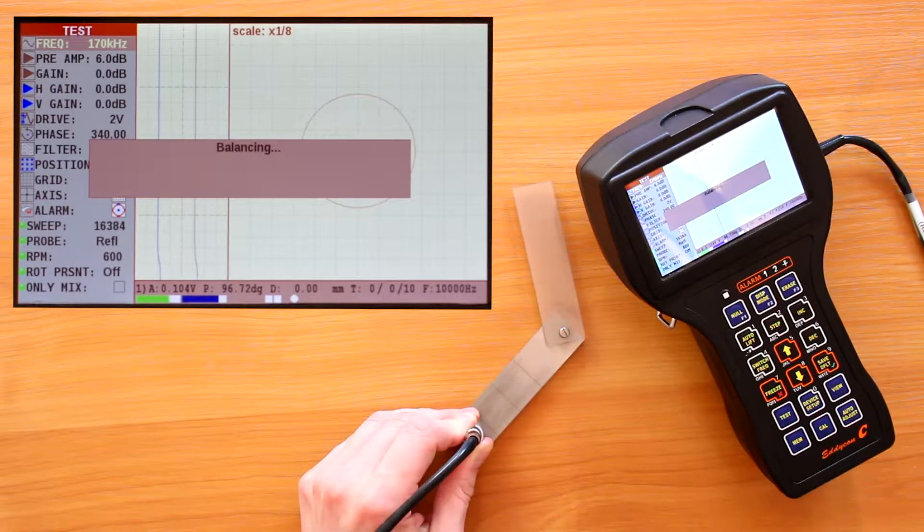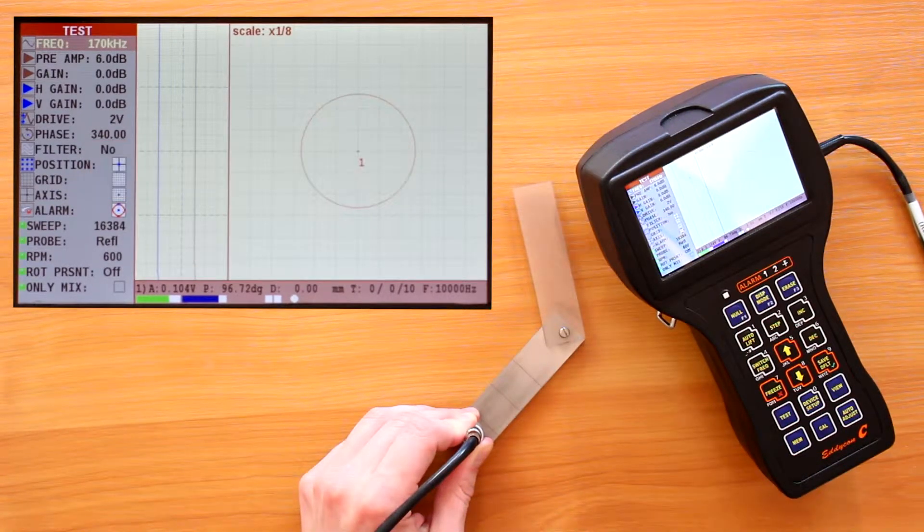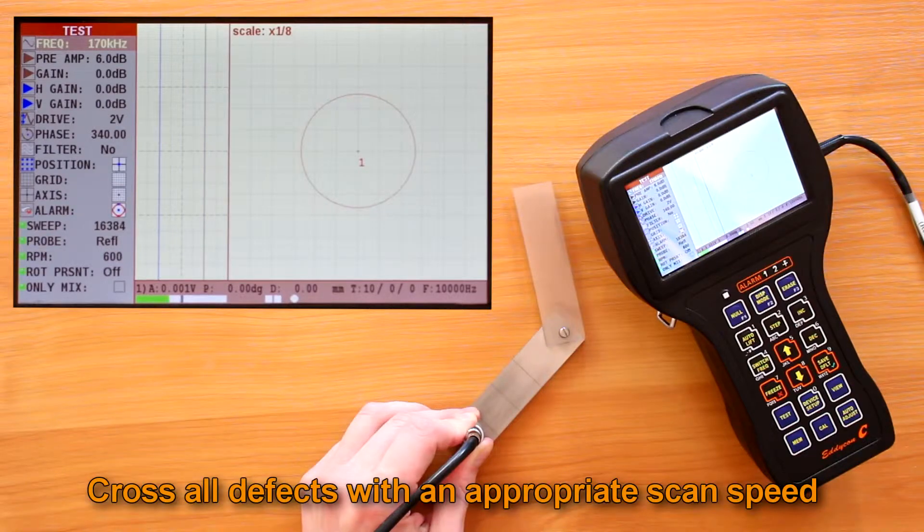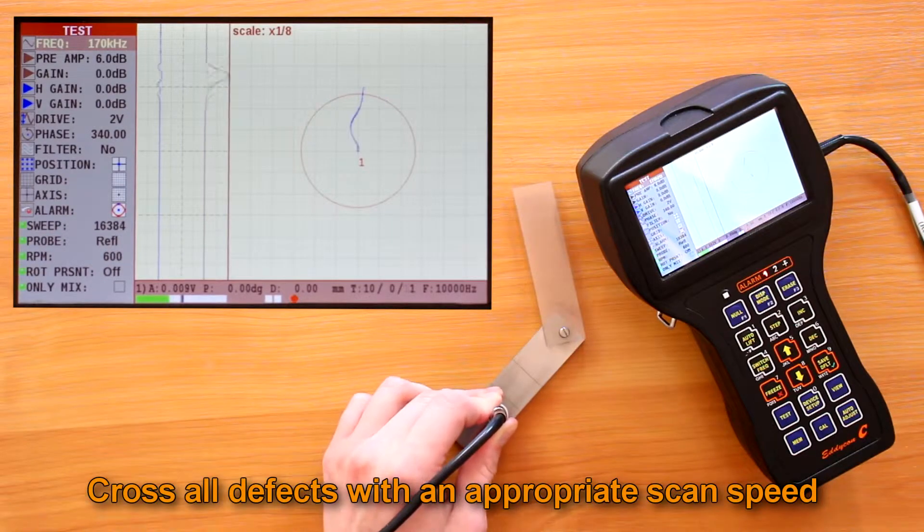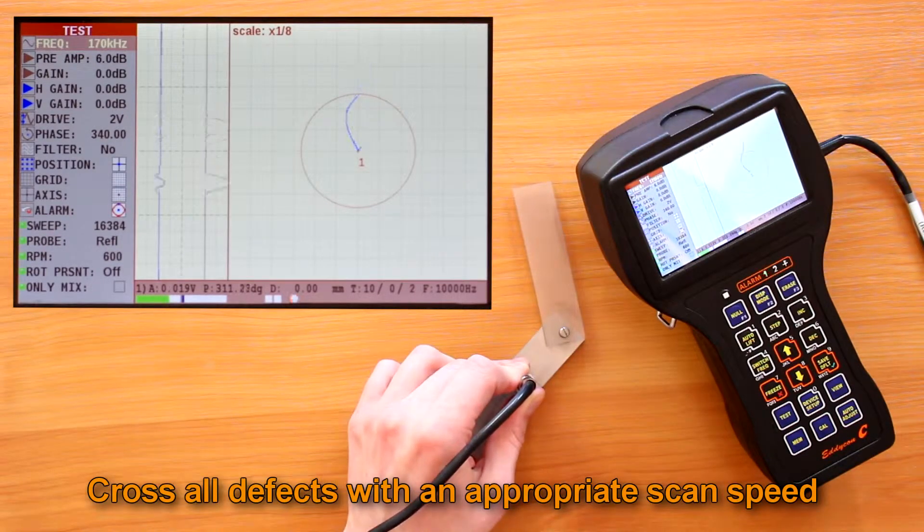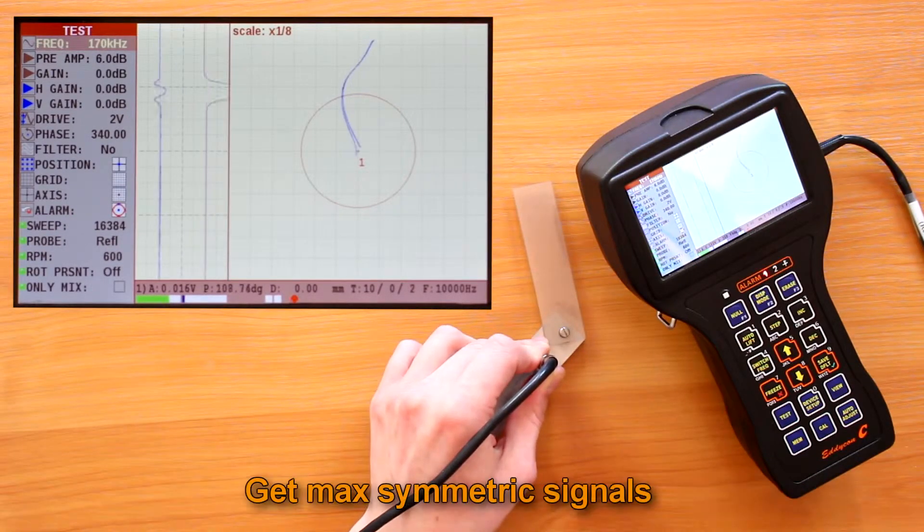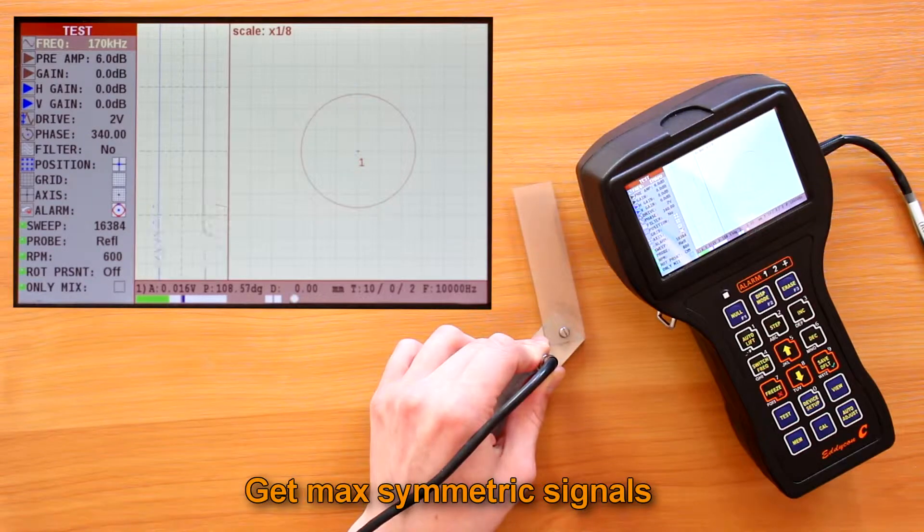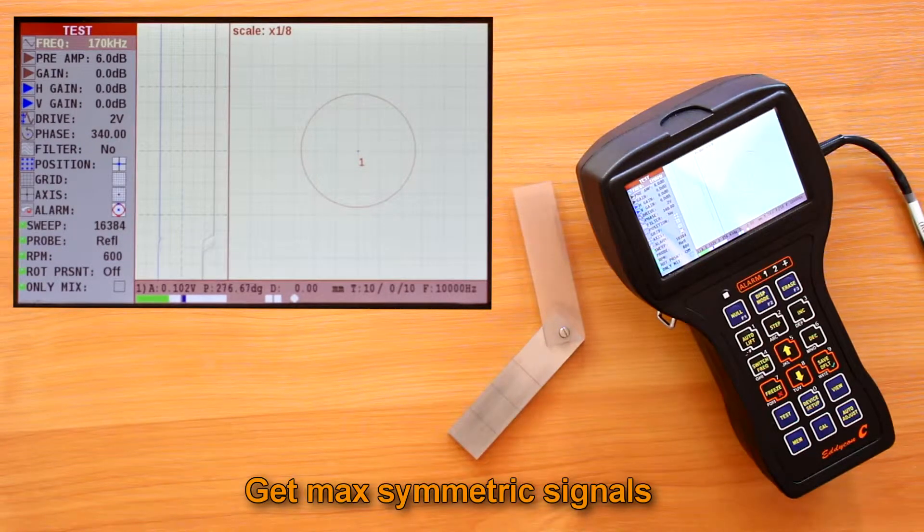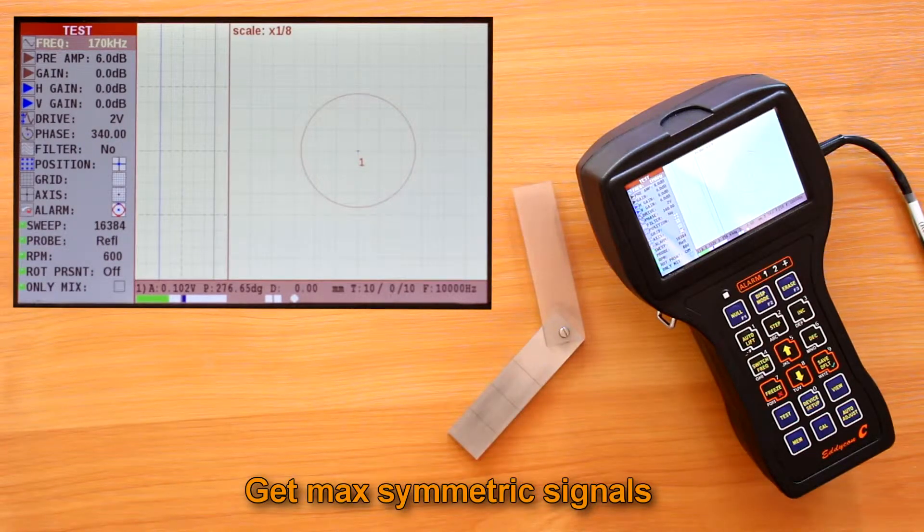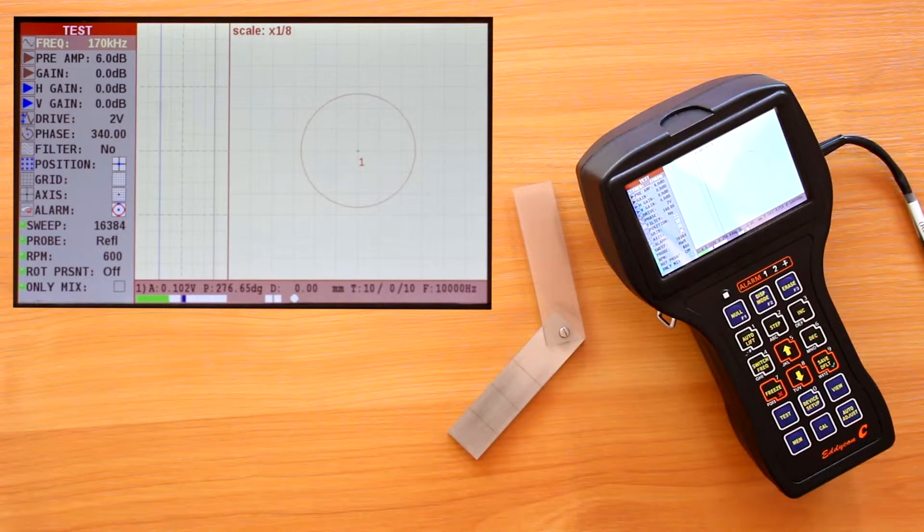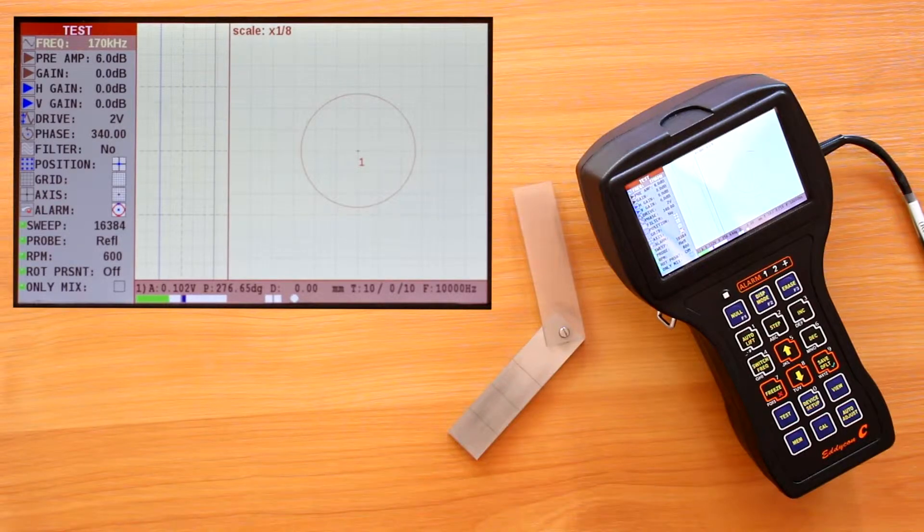Then you have to cross all defects with an appropriate scan speed to get all signals from the defects of regular shape—that is, max symmetric signals relative to their peak on strip charts. After defectogram acquisition, press the calibration key to quickly navigate to the calibration menu.